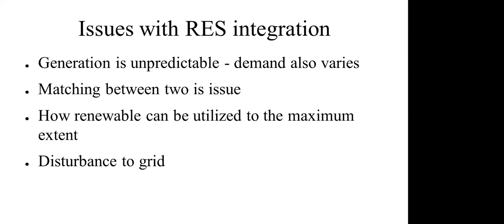Now, this is the issue generally found when a renewable source is connected to a system. It's reverse power flow, and it becomes a problem for the protection system. If you consider top-to-bottom power flow, and a renewable source is connected to a distribution system with loads at the other end of the protection system, then your relays may see reverse power flow. Then your relay may trip, so it has to be properly reconfigured if you have renewable sources in the distribution system. And power quality issues will always be there.